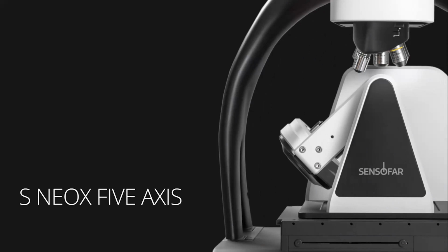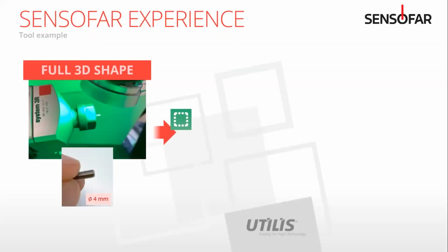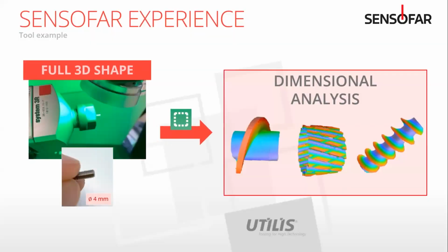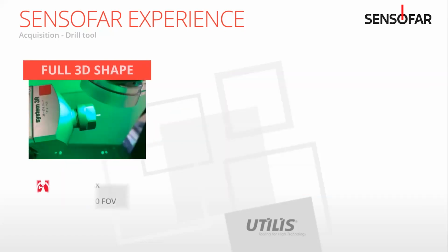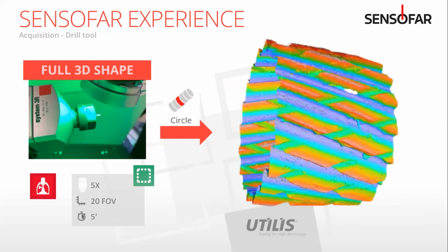But I just wanted to briefly go over how using the 5-axis gives you more options for automation as well. So our 5-axis unit, as I mentioned earlier, allows you to characterize the full 3D shape of something. So a tool, a bone screw, something small and cylindrical can be completely characterized by the 5-axis. So you just place the tool in there, and then after you've set up a recipe, it will do that automatically for you. So you can then look at it.